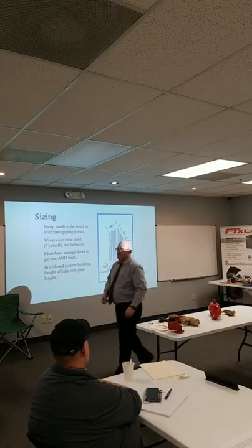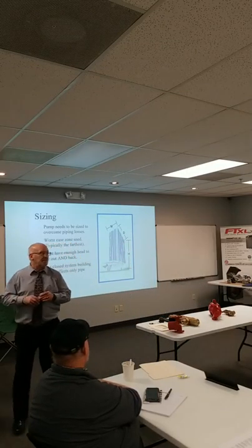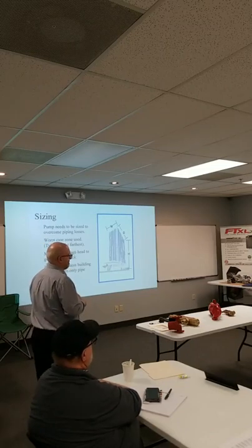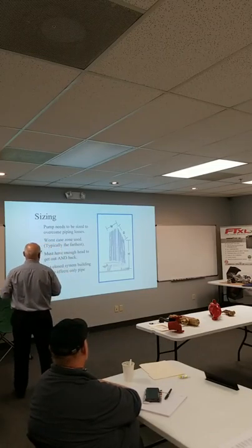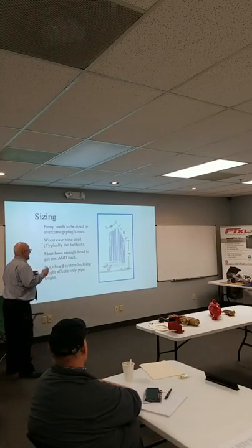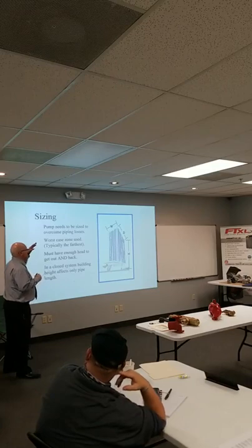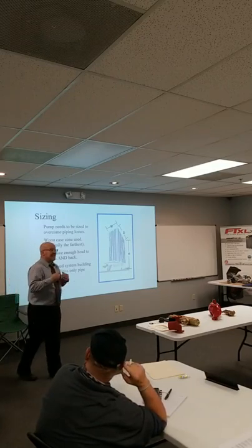Yeah, so 175 PSI times 2.31, because that's what you're going to see on the gauge when it's just sitting there off. You're going to see the static, that column of water. But again, I don't care from a pump perspective whether that building's 200 feet tall or 200 feet long. It's the same pump head.